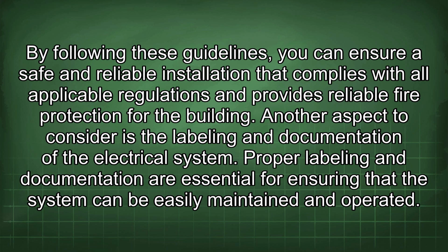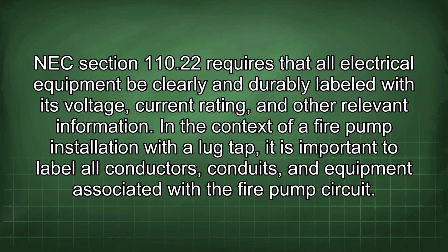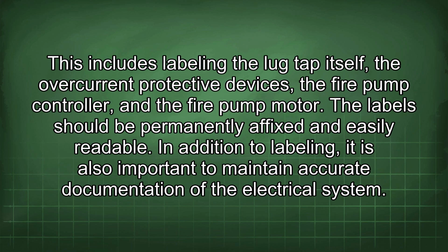Another aspect to consider is the labeling and documentation of the electrical system. Proper labeling and documentation are essential for ensuring that the system can be easily maintained and operated. NEC Section 110.22 requires that all electrical equipment be clearly and durably labeled with its voltage, current rating, and other relevant information. In the context of a fire pump installation with a lug tap, it is important to label all conductors, conduits, and equipment associated with the fire pump circuit. This includes labeling the lug tap itself, the overcurrent protective devices, the fire pump controller, and the fire pump motor. The label should be permanently affixed and easily readable.